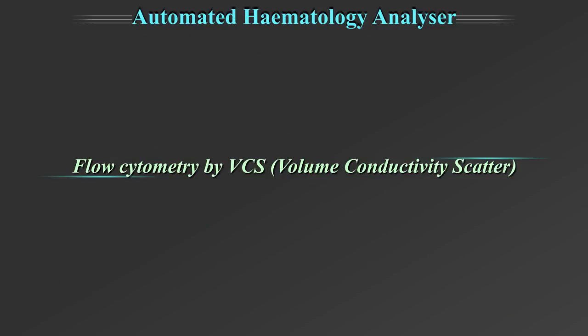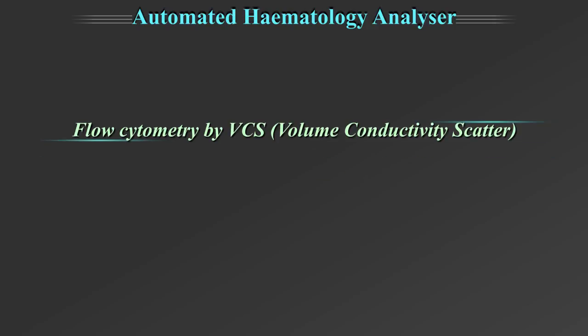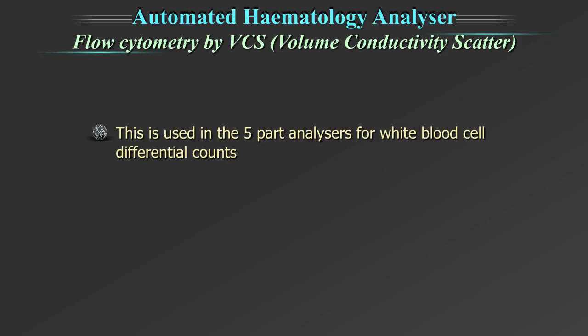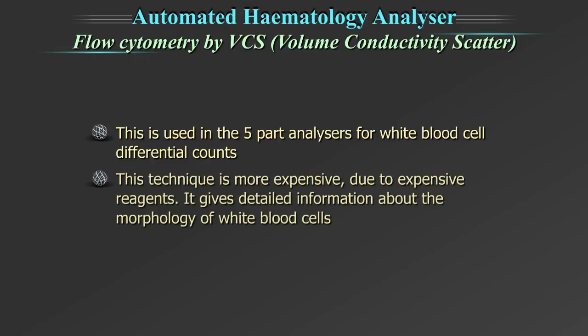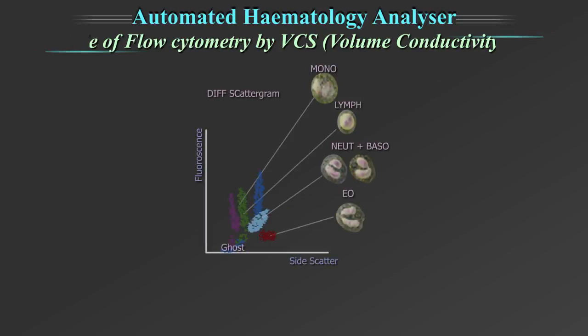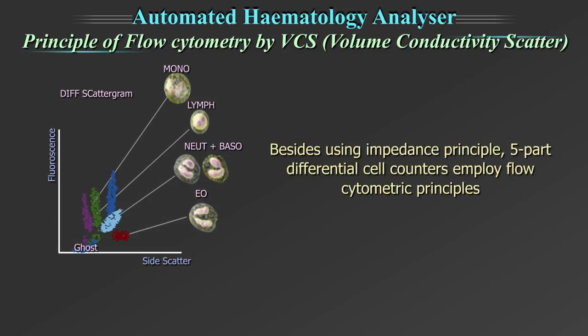The third technology is flow cytometry by volume conductivity scatter, or fluorescent flow cytometry. This is used in the five-part analyzer for white blood cell differential counts. This technique is more expensive due to the expensive reagents, but gives detailed information about the morphology of white blood cells. Besides using the impedance principle, five-part differential cell counters also employ flow cytometric principles.